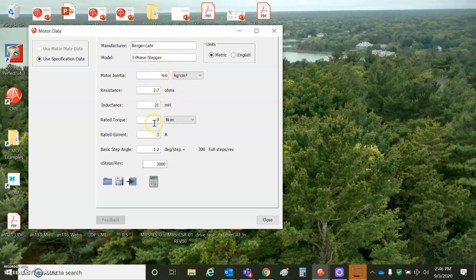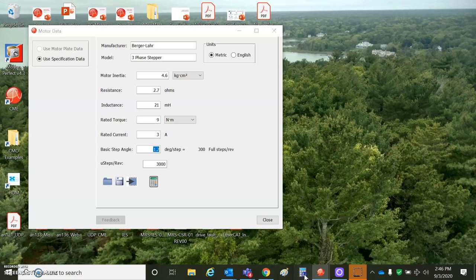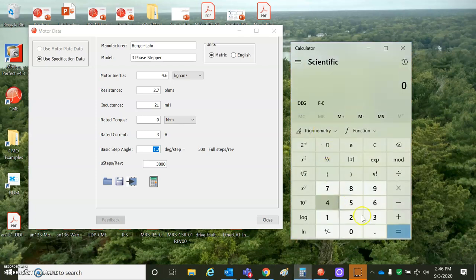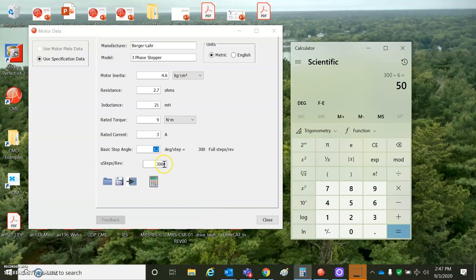Now, take a look at the motor data. Big inertia, inductance, resistance, 1.2 degrees, 300 full steps. So when I go to the current loop, the manual phasing screen and rotate the current vector, I'll have to rotate it six times for one electrical cycle. And so based on how many electrical cycles I find, 300 divided by six here in this case, it'll take 50 spins of the manual phasing dial to get one rev of the motor. Six ways to hook up the power to the wires, that's 300 full steps.